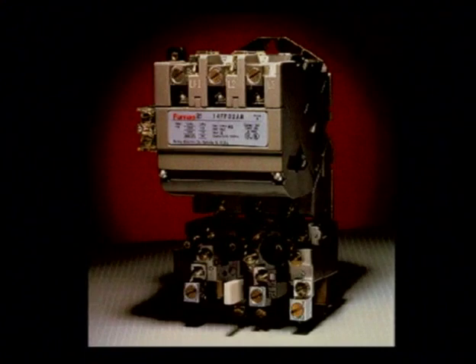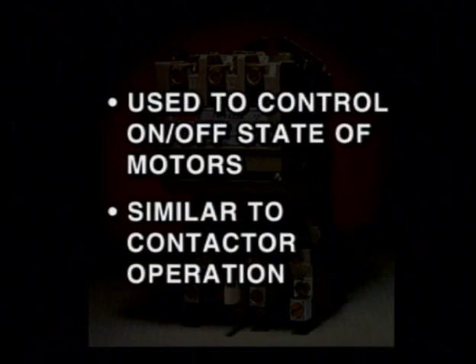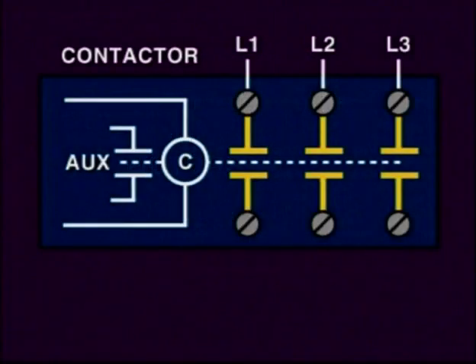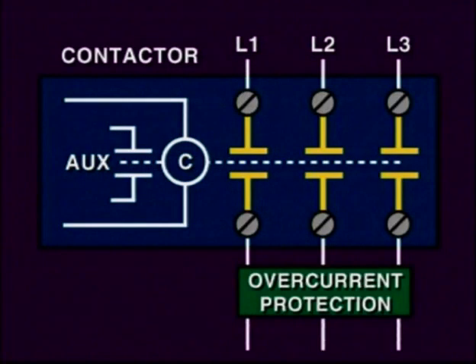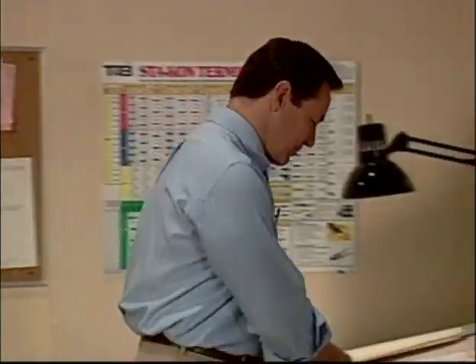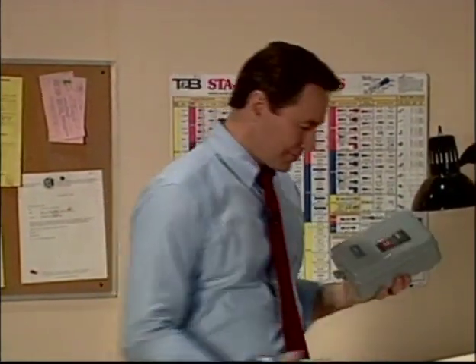Motor starters are one of the most widely used control devices in industry. As the name implies, they are used to control the on-off state of motors in a manner similar to the operation of contactors. In fact, the main difference between motor starters and contactors is the use of added protection devices for the motor to avoid overcurrents which could damage the motor under overload conditions. There are two types of motor starters: the manual motor starter and the magnetic motor starter.